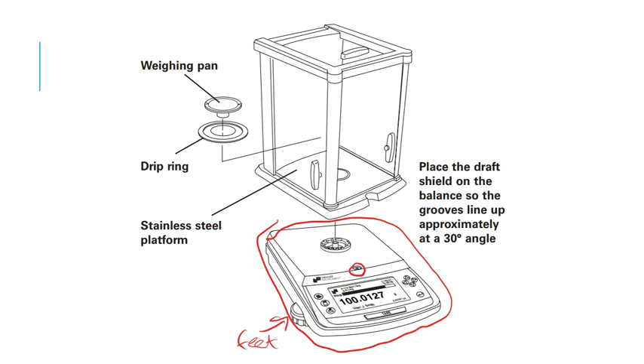On top is what we call the draft shield, this glass encasement that prevents drafts from happening, protects the sample from you, and protects you from the sample. These just sit on top, lowering down onto the middle of the base, and then you normally twist them. That twist somewhat locks them into place so they don't freely lift off without a little effort on your part.